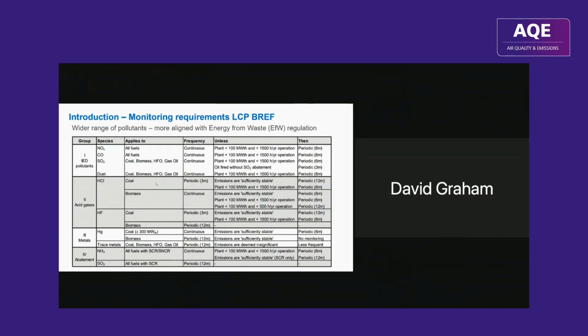The LCP BREF also introduces a wider range of pollutants for large combustion plants, more aligned with energy from waste regulation now. We've got the traditional pollutants at the top left there, NOx, CO, SO2, dust. And to that, for certain fuel types, are added HCl and HF, acid gases, mercury. And for plants fitted with SCR or SNCR NOx abatement, it's also ammonia and SO3 as a periodic measurement. So most of these are measured continuously under certain circumstances for certain fuels.